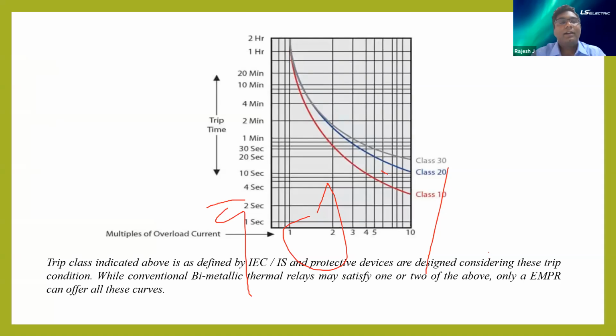I'm sure you all have knowledge about this trip class. So now my question is how to protect the motor. Basically the issue for a motor is overheating, under normal circumstances or at start condition. These are the basic problems for the motor. The overheating can be caused due to overload, phase unbalance, etc. So many reasons. So how to protect the motors?